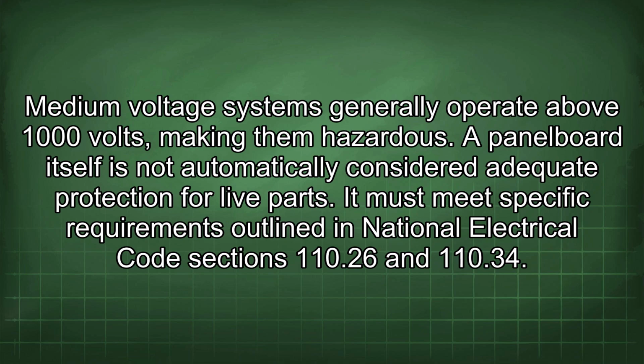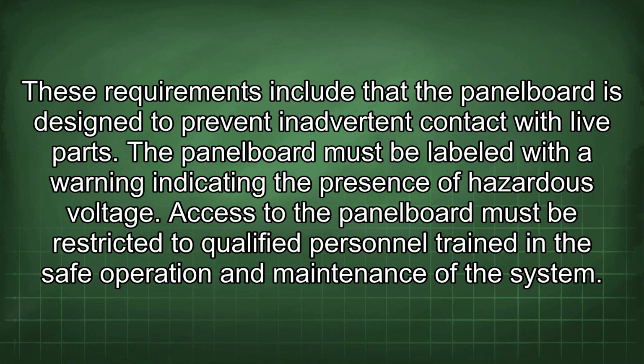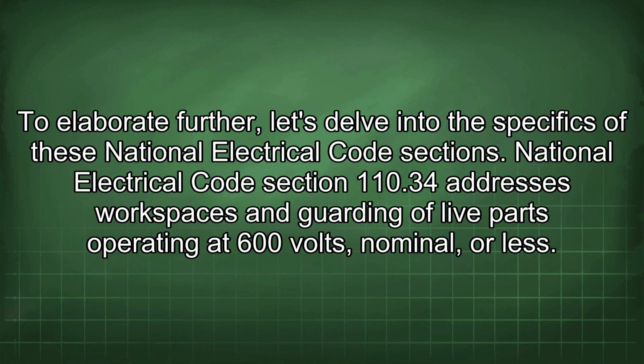A panel board itself is not automatically considered adequate protection for live parts. It must meet specific requirements outlined in National Electrical Code Sections 110.26 and 110.34. These requirements include that the panel board is designed to prevent inadvertent contact with live parts. The panel board must be labeled with a warning indicating the presence of hazardous voltage. Access to the panel board must be restricted to qualified personnel trained in the safe operation and maintenance of the system. To elaborate further, let's delve into the specifics of these National Electrical Code sections.